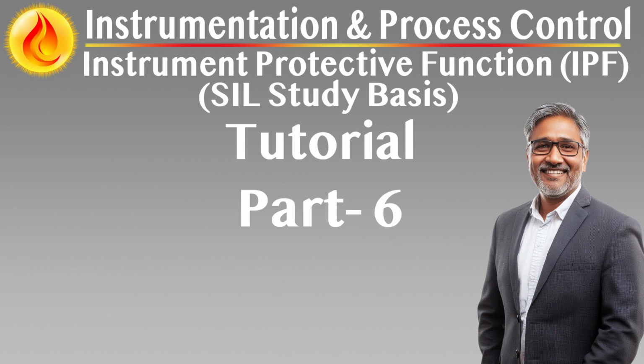Time-limited activation. Automatically expires after a preset duration to prevent indefinite bypass conditions. Configurable timers ensure the override window is long enough for task completion, but not unnecessarily extended. Restoration enforcement. System logic ensures the IPF cannot return to normal service until a function check is completed and all override conditions are cleared. Restoration may be confirmed through operator acknowledgement or diagnostic validation.